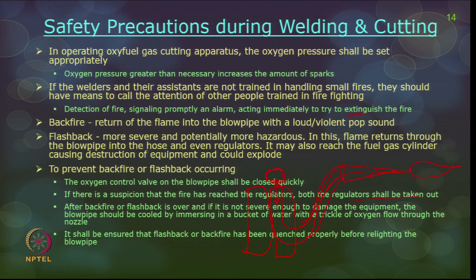If there is suspicion that the fire has reached the regulators, both regulators shall be taken off. After the backfire or flashback is over, maybe even after 60 minutes or so, you have to really check by immersing the blowpipes into a bucket of water, and check for the presence of any fire still existing. Only then should you restart the operation. So, it shall be ensured that the flashback or backfire has been quenched properly before relighting the blowpipe.